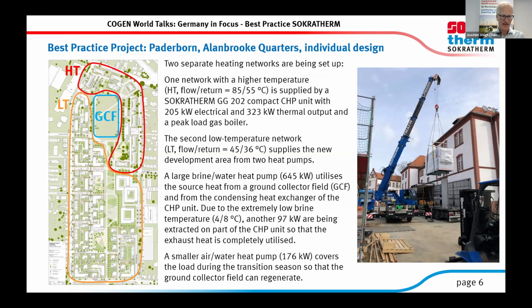On the one hand, the regeneration can be done by putting the collector field offline and using only the heat from the exhaust heat exchanger of the CHP, and the other possibility is using the air water heat pump. And so the ground collector field in the winter is always available with the necessary temperatures. Yes, so this was what I've been requested for today.